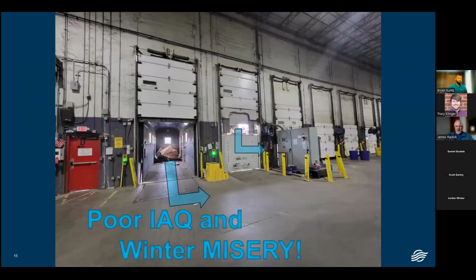Right there we go. This is a little bit stepped away picture of that same facility. You see there's a bunch of yellow pillars around there guarding that electrical panel. On the other side of the electrical panel is that door with the exhaust fan in it. What's going to happen in the middle of winter when it's cold outside, you've got wind blowing in against the building, or even just the negative pressure that's created within it when you don't have the proper makeup air for exhaust? Now, I'm not anti-exhaust. But I don't believe exhaust is prudent when you don't have a correct amount of makeup air to replace it, and actually enough makeup air to slightly positively pressurize it and start moving everything towards those points where you're trying to get rid of it.